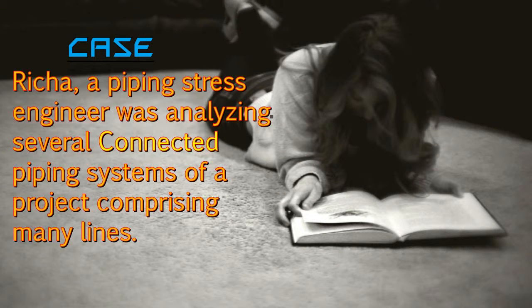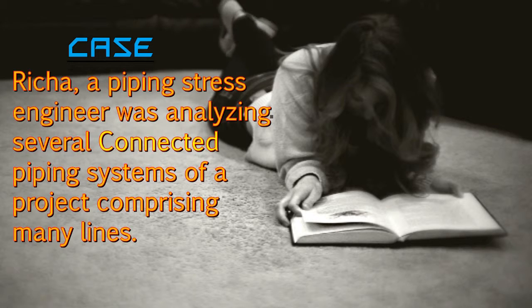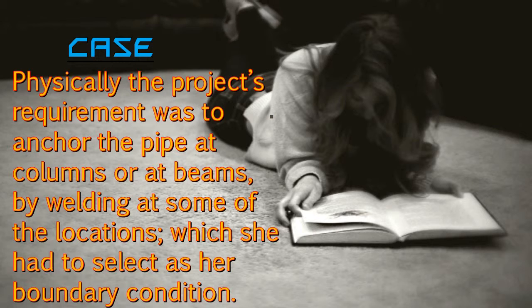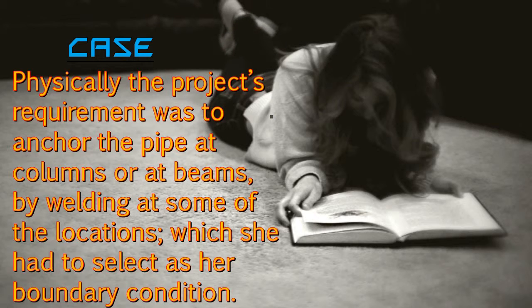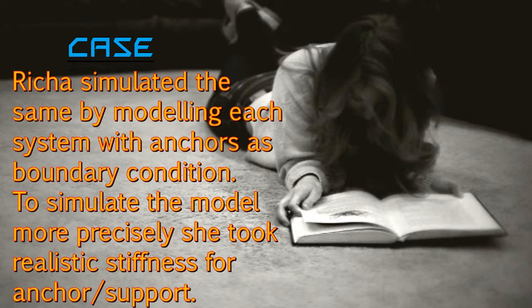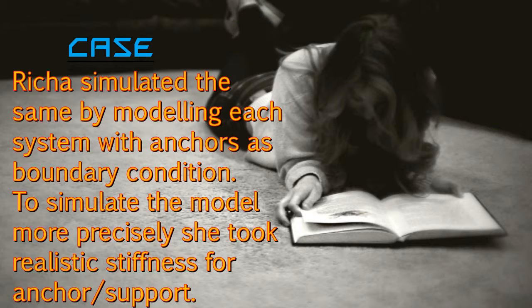Rich Ha, a piping stress engineer, was analyzing several connected piping systems of a project comprising many lines. Physically, the project's requirement was to anchor the pipe at columns or at beams by welding at some locations, which she had to select as her boundary condition. Rich Ha simulated the same by modeling each system with anchors as boundary condition, and to simulate the model more precisely, she took realistic stiffness for anchor and support.